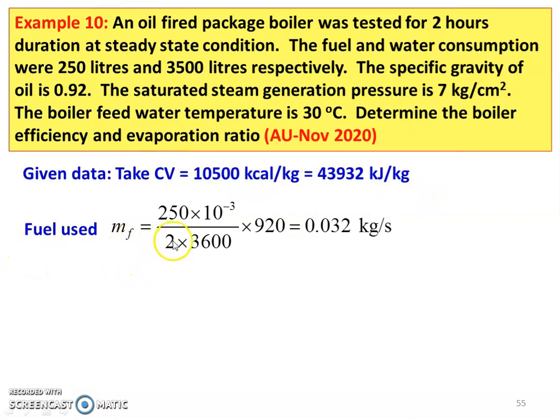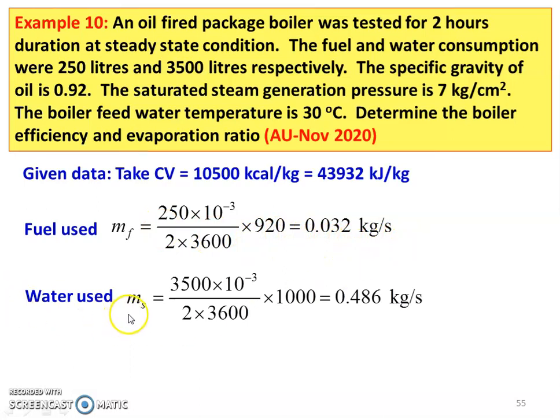Mass of the fuel used: MF equals 250 liters for 2 hours — that is the data given in the problem. So, 250 divided by 2, into 3600, into 10 to the power minus 3 to convert into cubic meters, into 920 to convert into kilograms per second. This gives 0.032 kilograms per second. Similarly, water used, or steam produced: MS equals 3500 liters for 2 hours. So, 3500 into 10 to the power minus 3 into 1000 to convert into kilograms, divided by 2 into 3600 to convert into seconds, which is 0.486 kilograms per second.